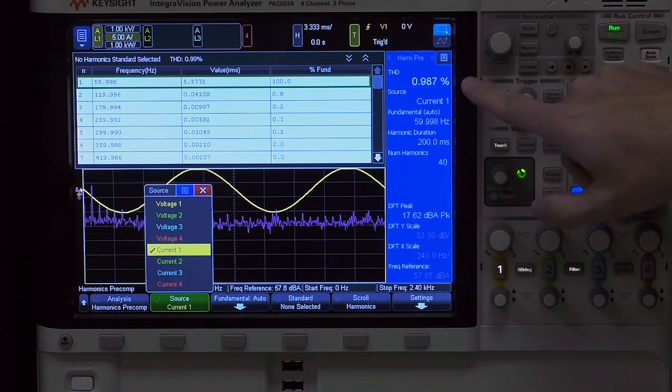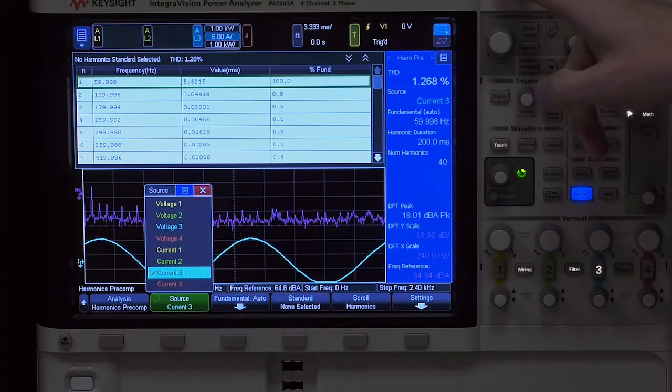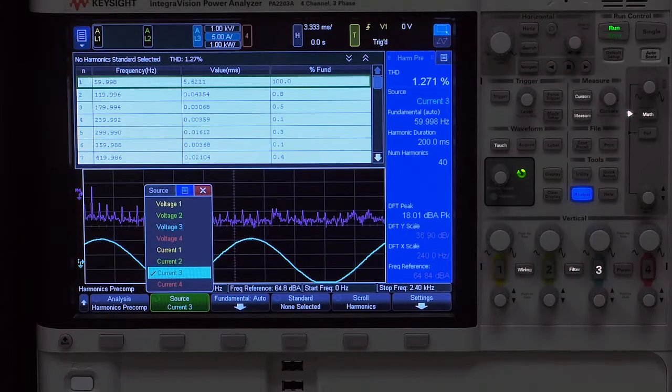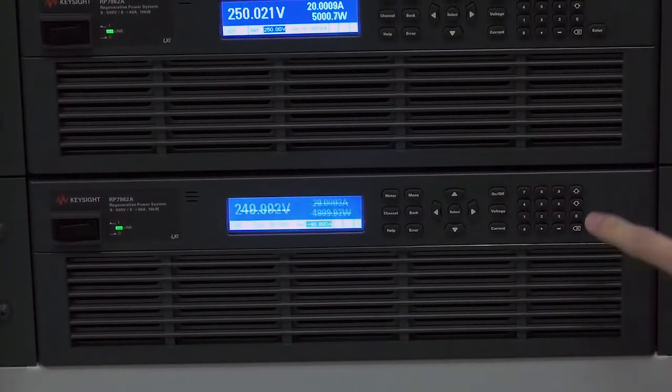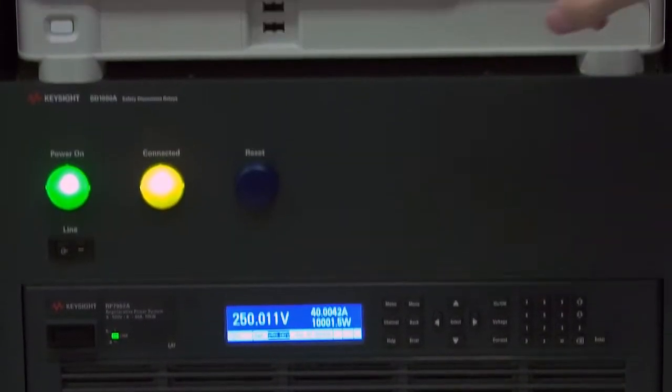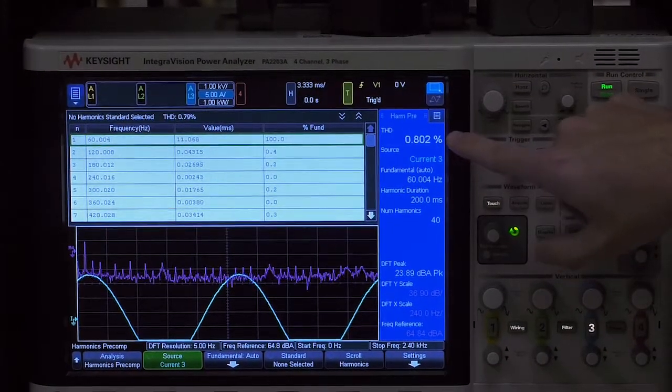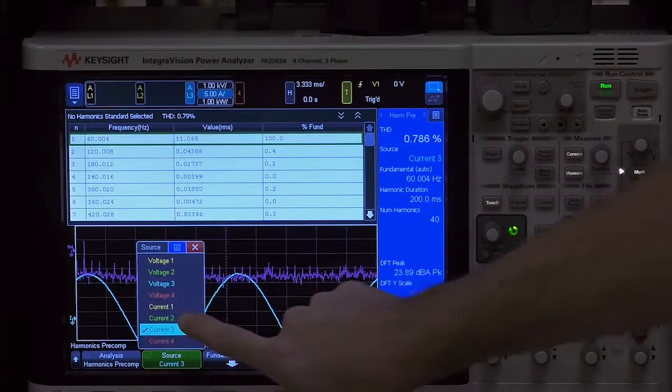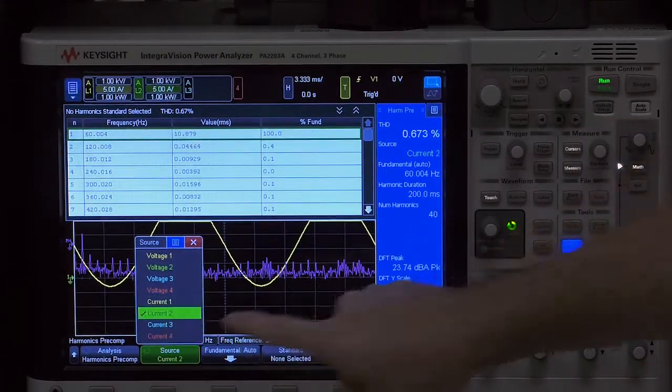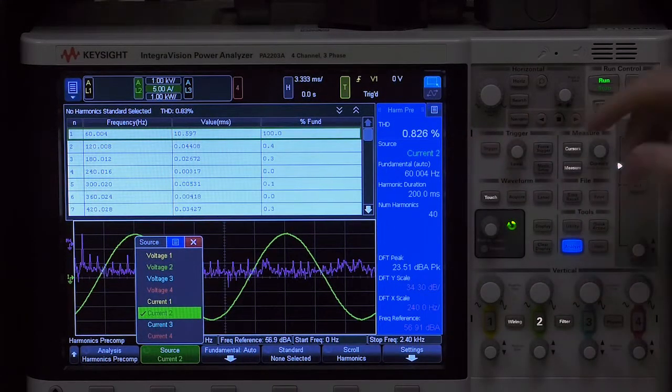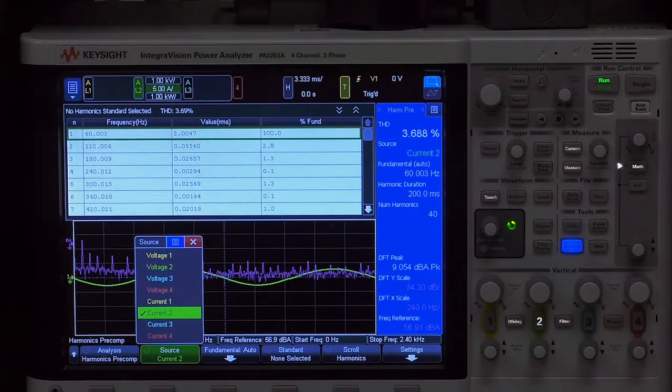1.2 percent. Again, this is at 5000 watts. Now these are 10 kilowatt power supplies, so if we go all the way up to 10 kilowatts, or 40 amps, you can hear the fan noise picking up to cool it. But you can see the THD actually gets even better. It's sub one percent, about 0.8 percent. And again, we can look at one of the other phases. 0.6 percent, again roughly the same. And then the last phase, 0.8 percent.